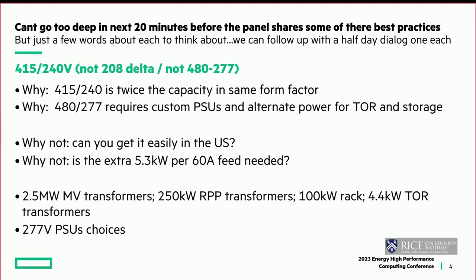If you're above 250, those power supplies are hard. You make the decision at the transformer. When you have medium voltage and you're putting in a new 2.5 megawatt service, instead of having to take the step down from medium voltage to 480-277, have them take it down to 415, 240, and then you're done.